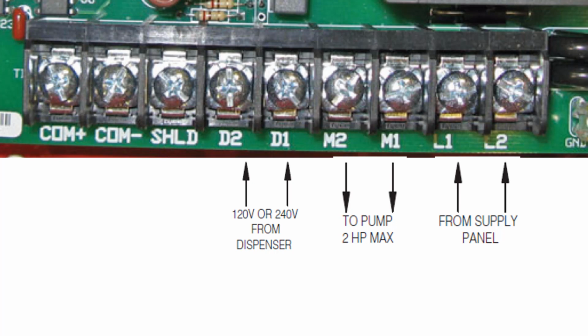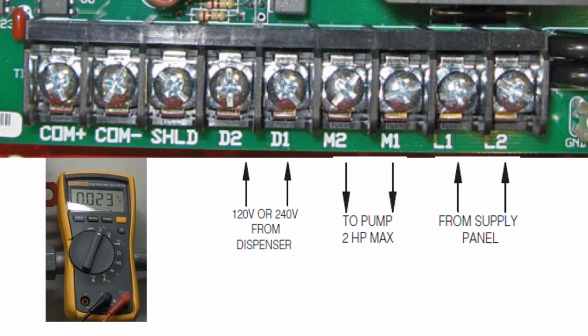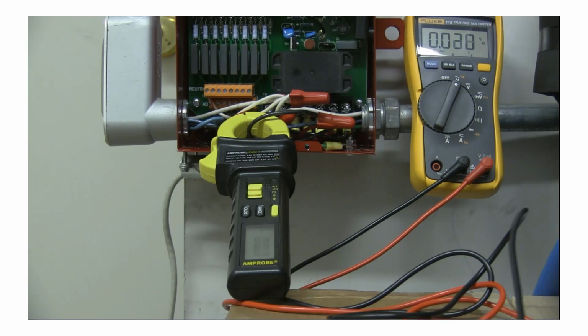You will need to energize the hook signal by lifting a nozzle on a dispenser. If you read voltage from the dispenser hook signal, verify the STP relay is closing by measuring the voltage across M1 and M2. If there is no output, you will need to repair the control box.